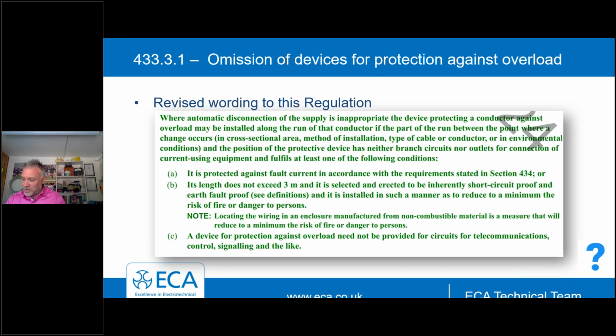In summary, protection against overload need not be provided where a conductor situated on the load side of the point where a reduction occurs in the value of current carrying capacity is effectively protected against overload by a protective device installed on the supply side of that point, or for a conductor which, because of the characteristics of the load or its supply, is not likely to carry overload current, provided that the conductor is protected against fault current in accordance with the requirements of section 434, or at the origin of the installation where the distributor provides an overload device that agrees that it affords protection to part of the installation between the origin and the main distribution point of the installation where further overload protection is provided, or a device for protection against overload need not be provided for circuits for telecommunications, control, signals, and the like.